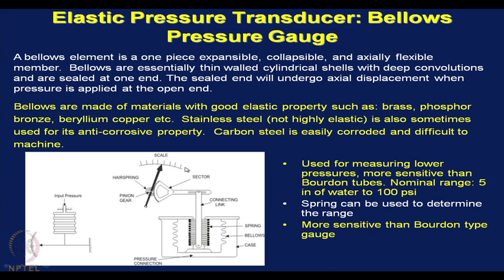Bellows are made of materials with good elastic property such as brass, phosphor bronze, beryllium copper, etc. They are all alloys. Stainless steel is also sometimes used. Although it is not highly elastic, because of its good anti-corrosive property, we sometimes use stainless steel. Carbon steel is not a good choice because it gets easily corroded and it is also difficult to machine.